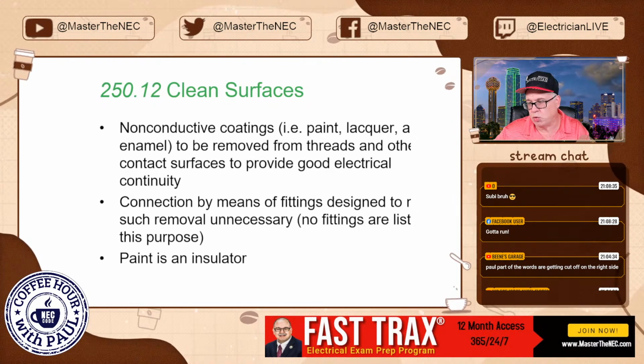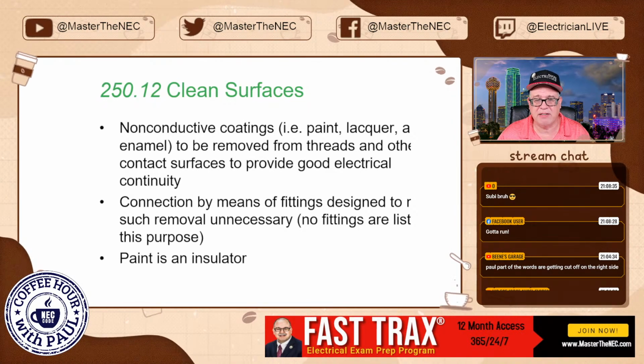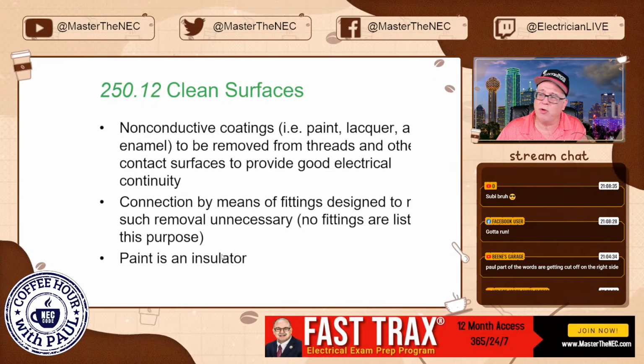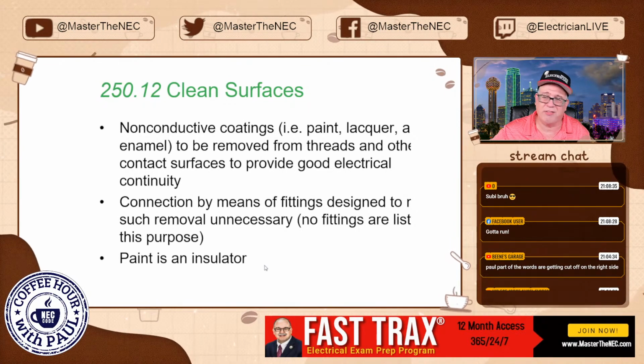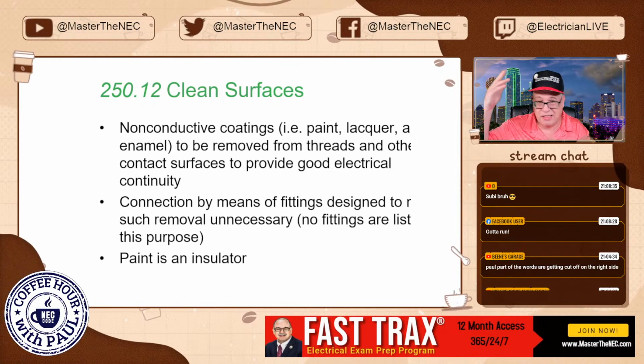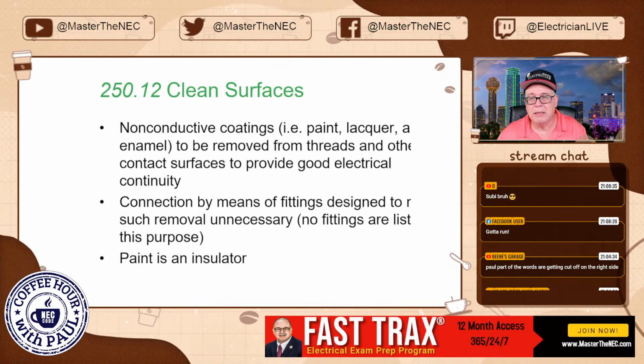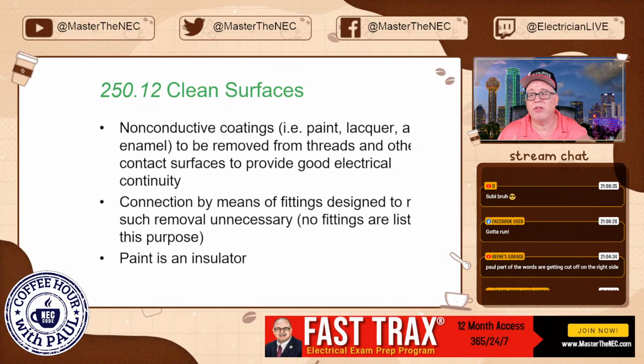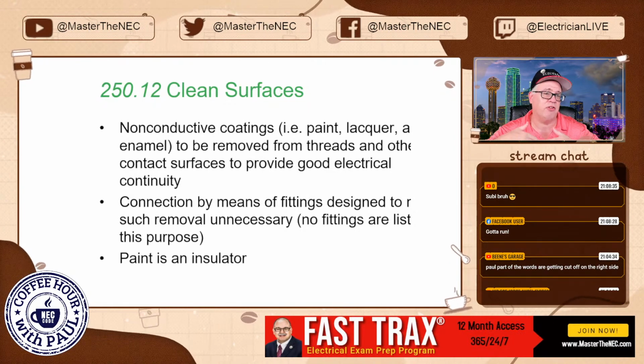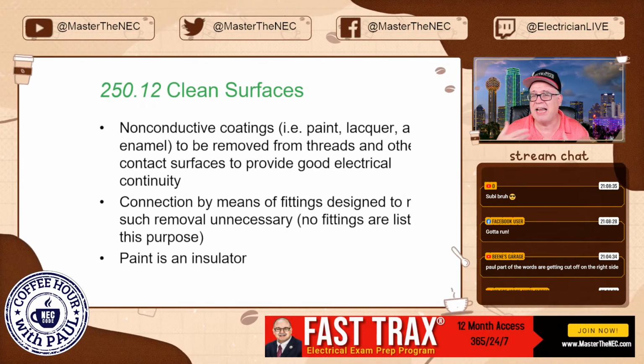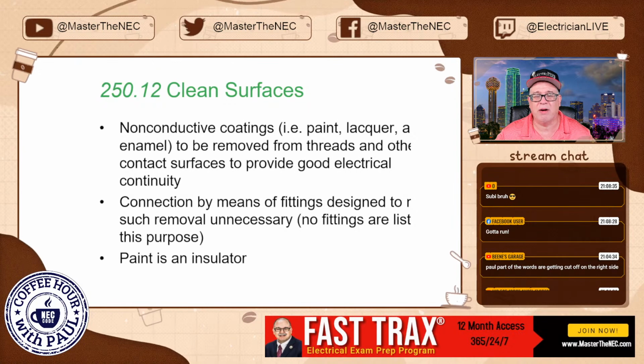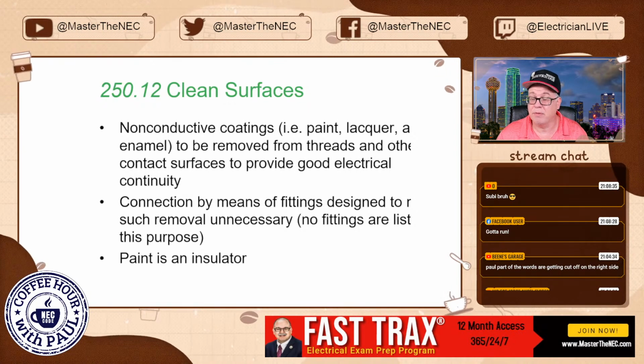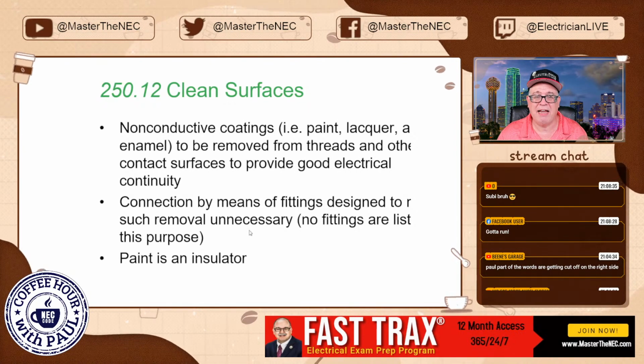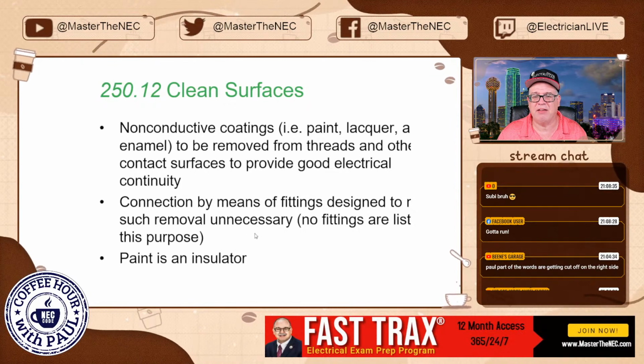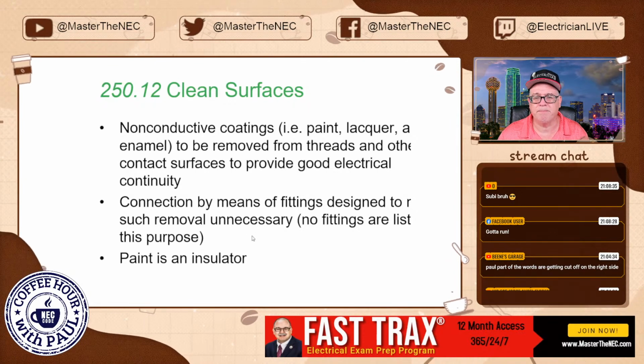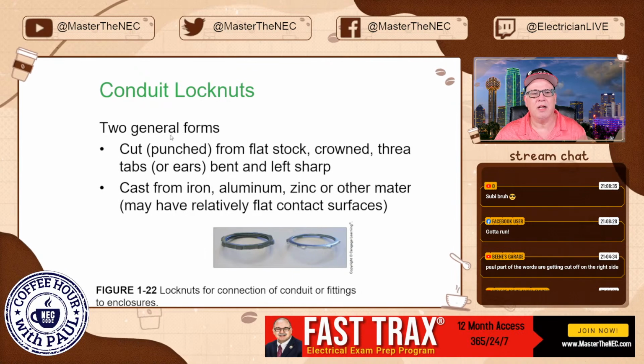We need to remove the paint where necessary to make these connections. Now, commercial applications, most of the stuff is stainless steel anyway. It's not painted. It's just stainless steel. Okay, well, then you're good to go. But you need to make sure that whether you're doing it in a residential situation, whether or not the paint or the enamel on that cabinet or whatever is conductive. If not, then you might have to have jumpers, or you might have to have things if somebody wants to argue that point.